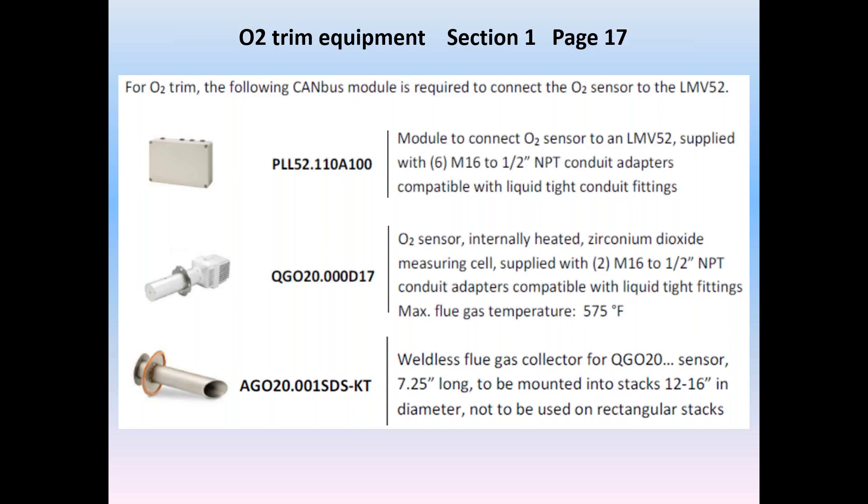Next is the O2 sensor itself, the QGO, suitable for natural gas or light oil. A QGO 21 is also offered for heavy oil. O2 is not suitable for digester gas operation. Third, the last element, is a collector, the AGO. It gets welded into the stack and holds the QGO oxygen sensor. A great option offered by SCC is a weldless collector. This features a gasket and the mounting hardware.